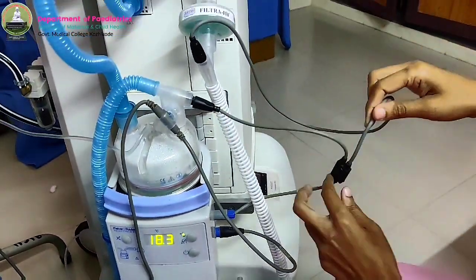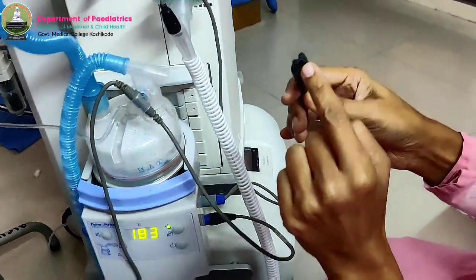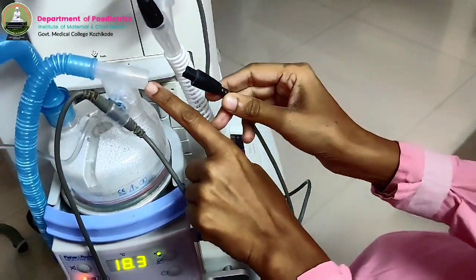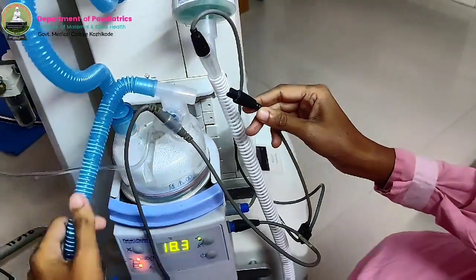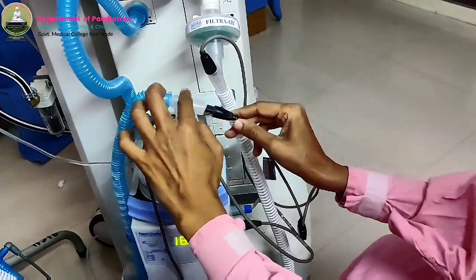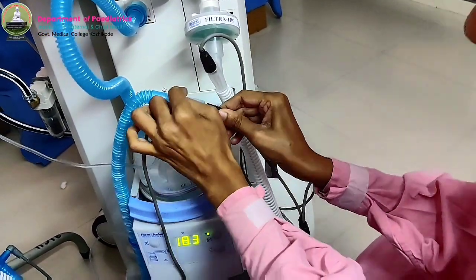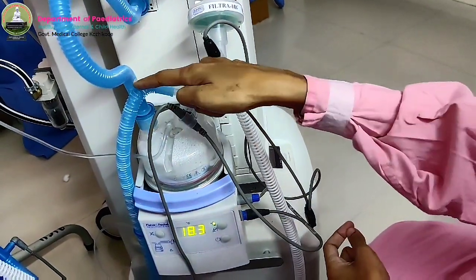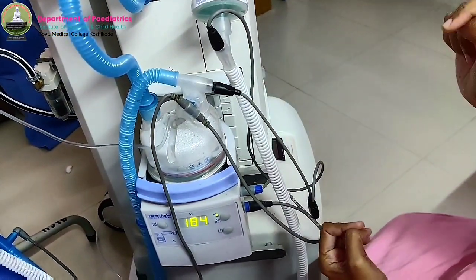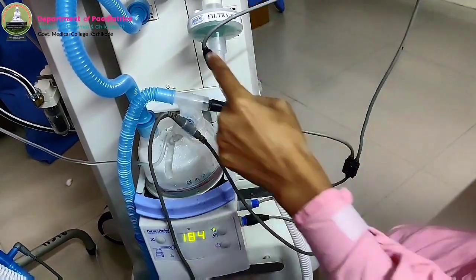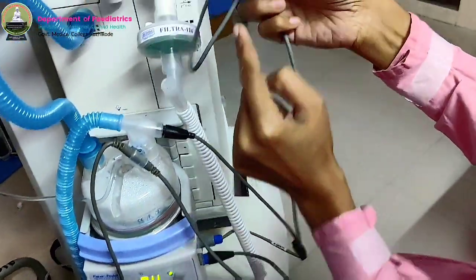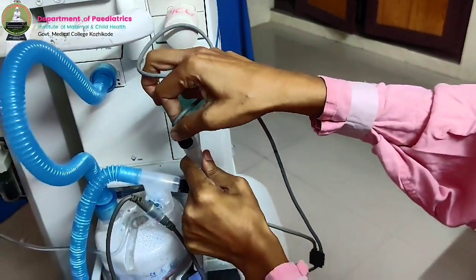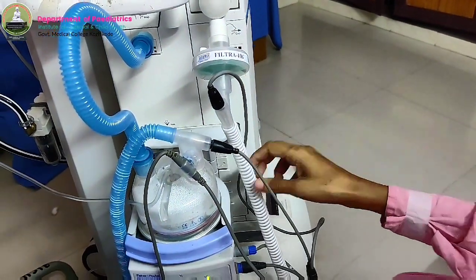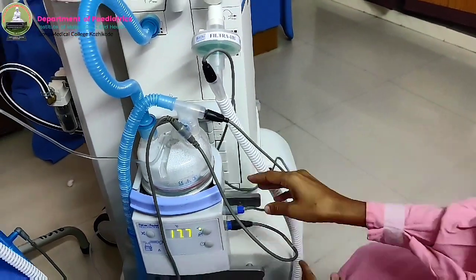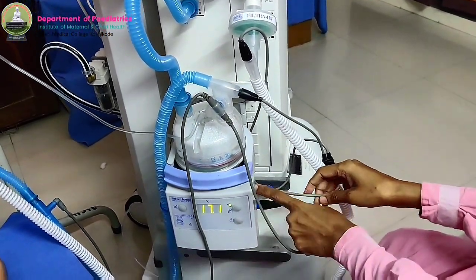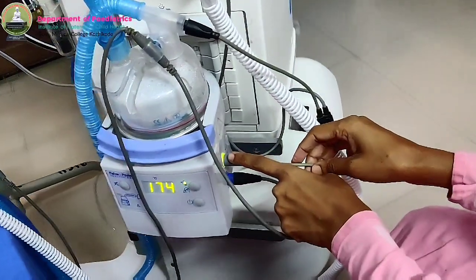into two. One has 3 pins, and that has to be connected to the end of the inspiratory limb near the humidifier. By connecting that, we are heating this wire with the help of current. Another cord is going and that is a double pin that has to be connected here. That wire heats the heating coil inside the expiratory limb. So this is the cord for heating. This yellow border you can see is the color code for the heating cord.